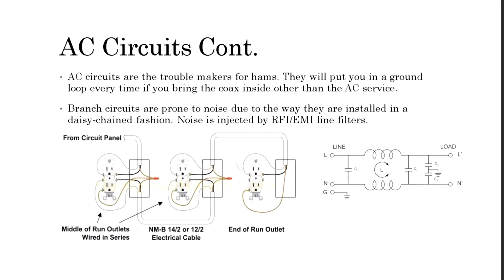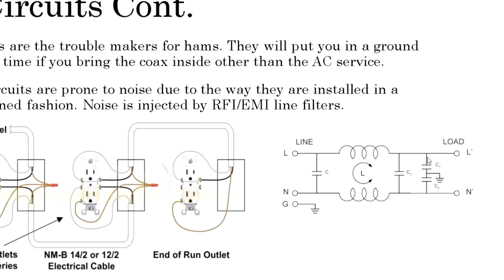Another room, say the living room, you've got a USB hub charger. All these things have line noise filters in them. And this guy right here, these two capacitors are real troublemakers. If you look, you've got a 0.1 microfarad capacitor hanging from line directly to ground. Well, that's injecting 60 hertz current directly into your ground circuit, okay? And all that is doing is going back on the ground wire, back to your breaker panel over here, and returning back to the utility neutral. It's current being put on your ground for nothing. It's just a noisemaker, okay? We cannot remove these line filters, but what we can do is get rid of the daisy chaining, and all we have to do to get rid of most of these problems is put in a dedicated AC circuit.